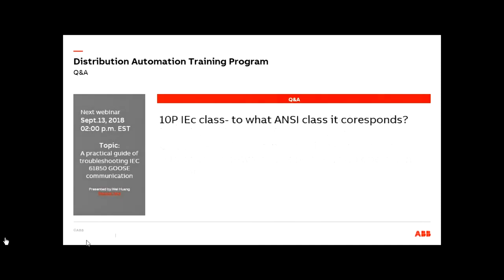Next question. The 10P class, to what ANSI class does it correspond? Great question again. The 10P class is IEC nomenclature. For ANSI, I don't have an exact number. It could be that the ANSI standard goes with the C200, C500 type of CTs. That could be the CT which could be chosen, and we have calculation examples for it depending on the machine size, which we can probably share with you.